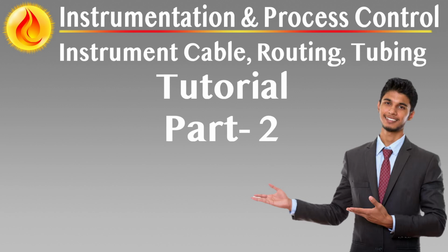Construction teams must prepare drum allocation and takeoff schedules in advance to optimize cable utilization and minimize scrap. Slack must be incorporated into every cable run, especially at riser points or building transitions, to absorb differential settlement and thermal expansion. Cables must never be clamped to process equipment, piping, ladders, handrails, or structural steel. Instead, they should be supported via designated brackets, trays, or trunking systems.